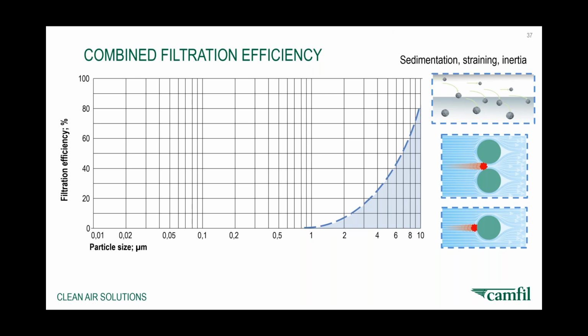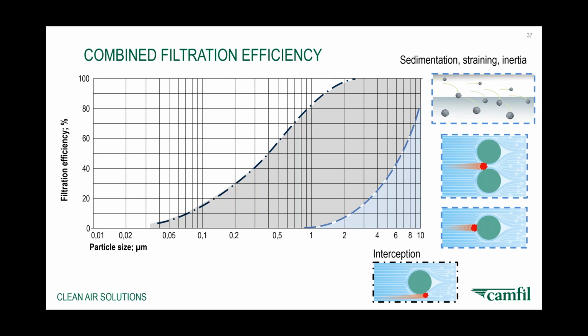So we look at the various effects that happen in a filter. As we said earlier, you've got sedimentation, straining, and inertia, which are for larger particles. The interception effect is when particles are moving and they try to get around the fibers, and they're attracted by various forces and they are caught by the media. As the particle gets smaller and smaller, these particles move very similar to chemicals, and they move in what's called Brownian motion. And here they move and are trapped with what's called the diffusion effect, that they move erratically. They don't move with the airflow, so the air is not actually moving them through the filter. They're moving erratically with what's called Brownian motion, but they still collide with the many fibers that are in a filter.